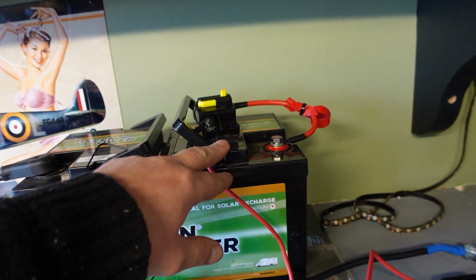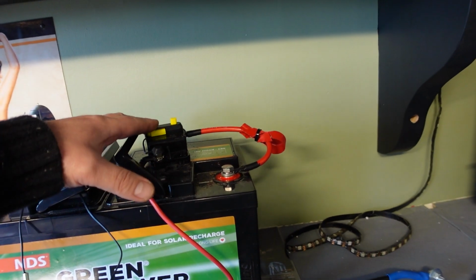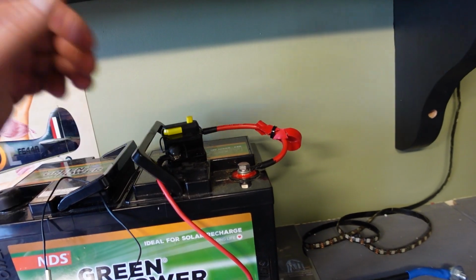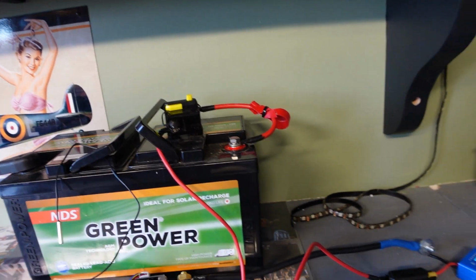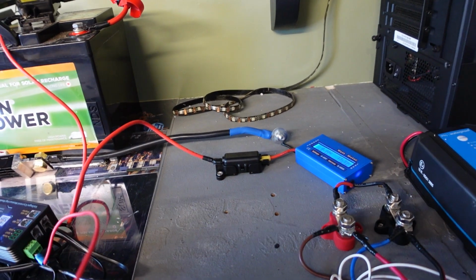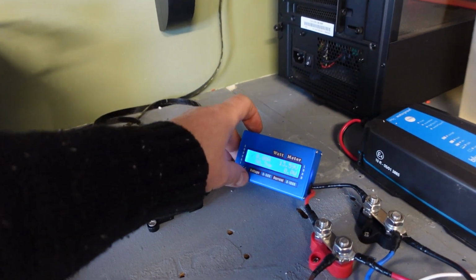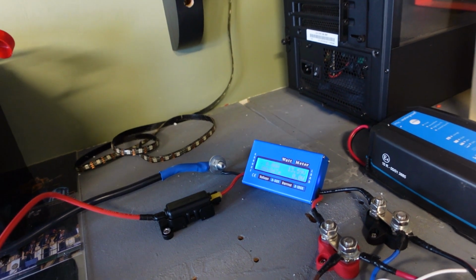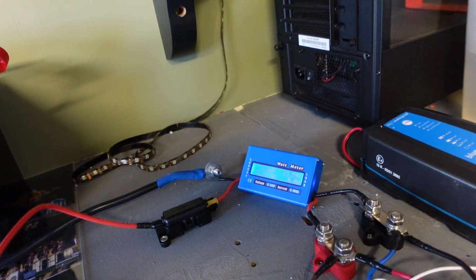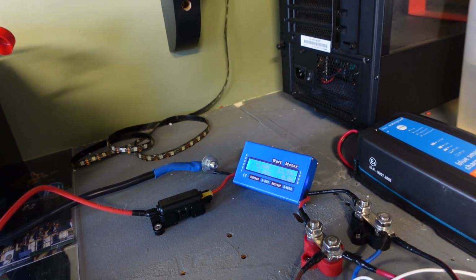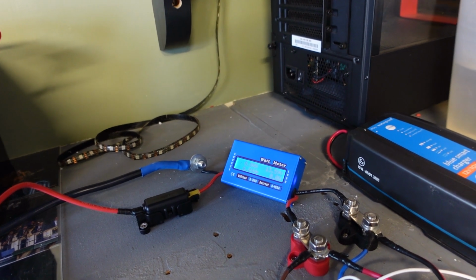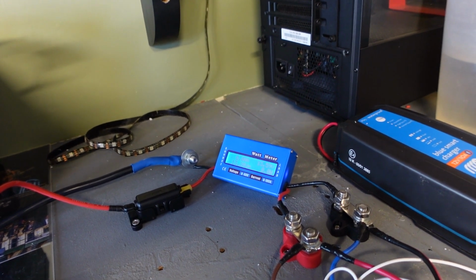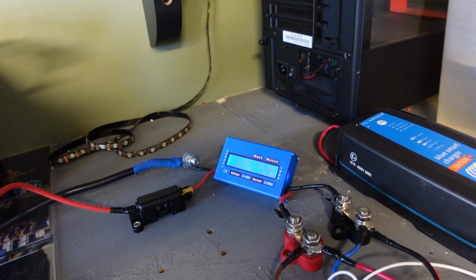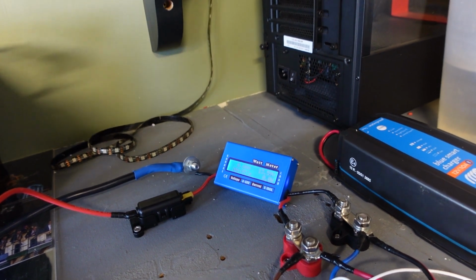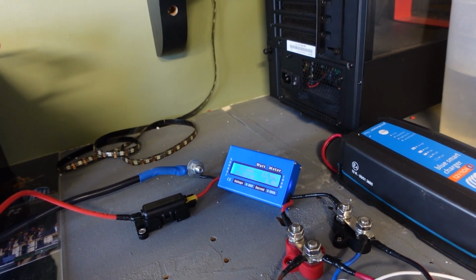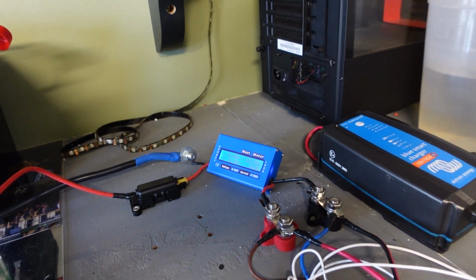On my positive side I've got an isolator to be able to isolate the circuit in case anything goes wrong. That's going down to a fuse. I've got a watt meter here which will give me amperage and amp hours of anything coming out of the battery. It's not a two-way watt meter, so it'll only read coming out, giving me an indication of how good the gauge's calibration is, because I've used these before and tested this one against my Fluke, and it's quite accurate.